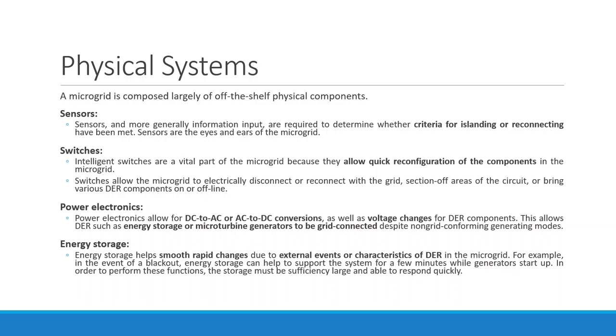Another part of the physical system is energy storage. Energy storage helps smooth rapid changes due to external events that are characteristic of DERs in the microgrid. When we talk about distributed energy resources, particularly renewable generation, it is characterized by uncertainty, variability, and intermittency. What it means is that the generation is not constant, it is variable, and uncertain, it is not predictable. Basically you cannot say for sure that there will be constant generation for this particular one hour. So at that time energy storage might help the microgrid to remain connected with the main grid.